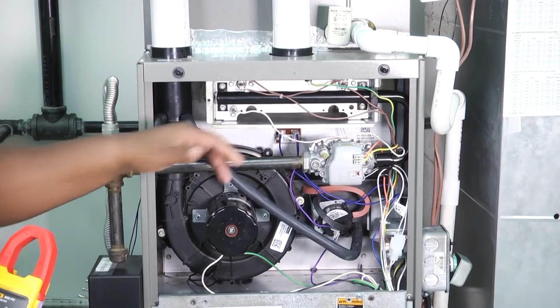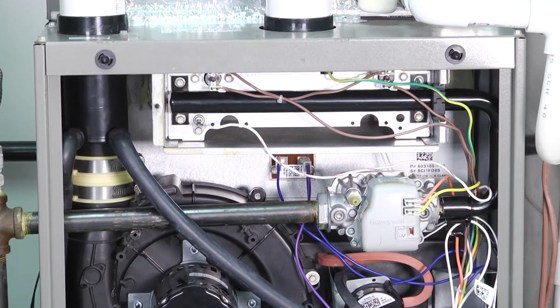Now, there's one other thing that you need to be aware of as it relates to flame sensors. You could be on an LP system, which is going to have a higher BTU content as far as the flame is concerned. Natural gas, we know, is going to put out 1,050 BTUs, whereas propane, you're going to be at around 2,400 BTUs. So it's a hotter burning fuel, if you will. Because of the temperature on a propane system, you could cause damage or see damage to where you've actually eaten away at the flame sensor.